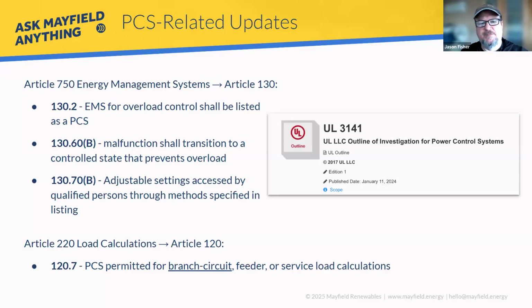That is, when you use a PCS for overload control, meaning I'm not using traditional load calculations or nameplate ratings of all my inverters to come up with my minimum ampacity and overcurrent protection. I'm going to use this PCS to manage the continuous current flow on these conductors regardless of what's connected to it, and size all my wires to that. That's overload control, and we've had a ton of success with it across the code. Very excited about all this.